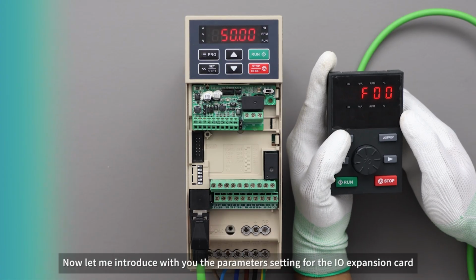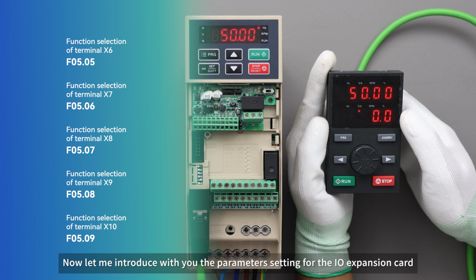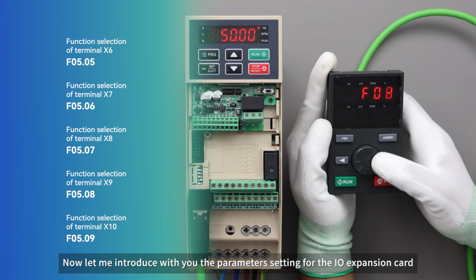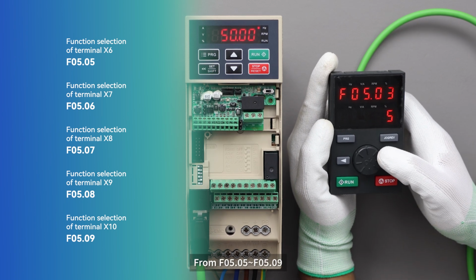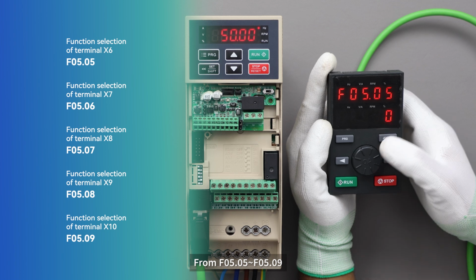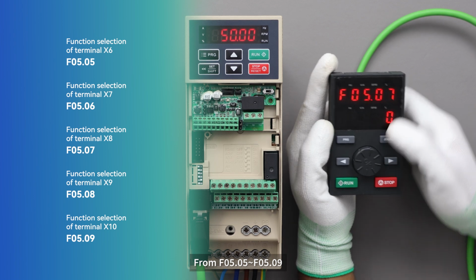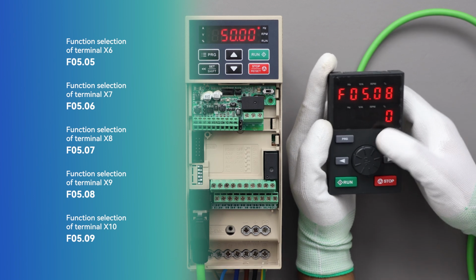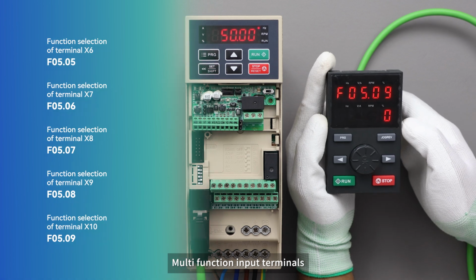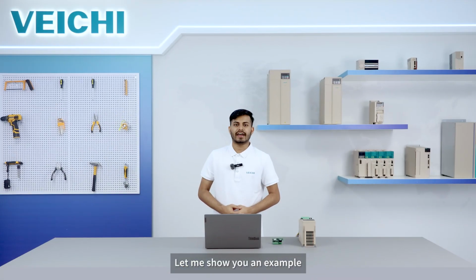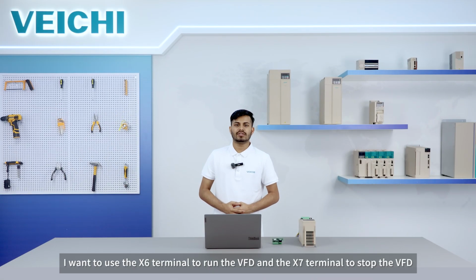Now let me introduce with you the parameter setting for the I/O expansion card, from F05.05 to F05.09 multifunction input terminals. Let me show you an example. I want to use the X6 terminal to run the VFD and the X7 terminal to stop the VFD.